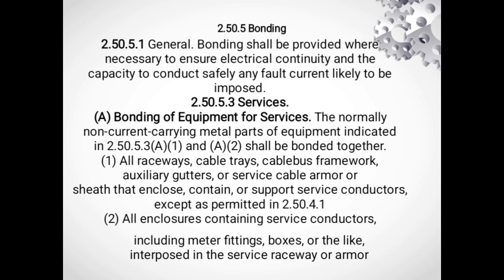2.50.5 Bonding. 2.50.5.1 General. Bonding shall be provided where necessary to ensure electrical continuity and the capacity to conduct safely any fault current likely to be imposed.